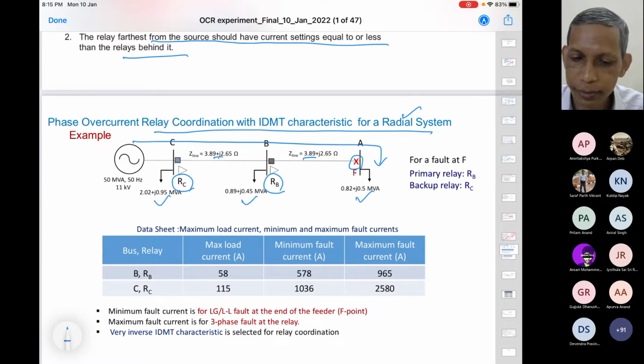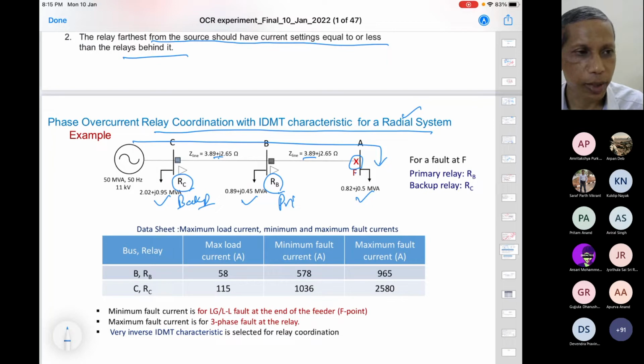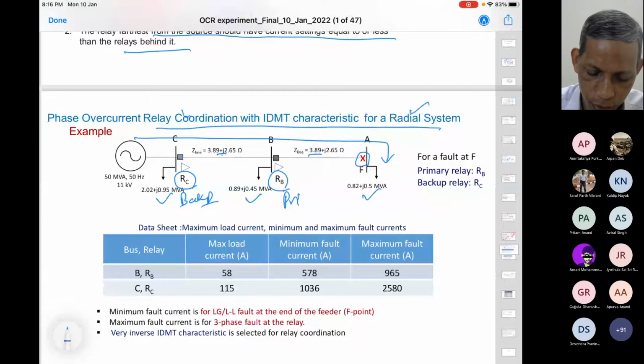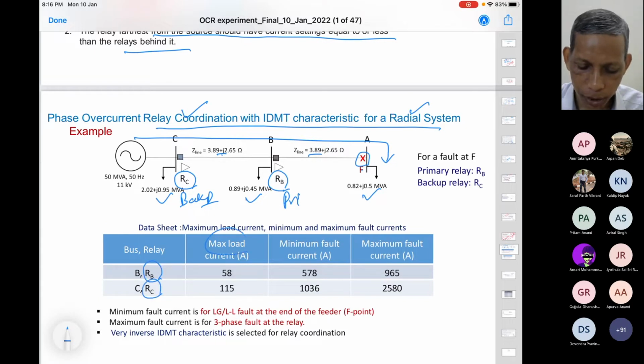For a fault at F, RB is the primary and RC is the backup. RB is the primary and RC is the backup. Agree? So that we have to see from that perspective. Okay. So if you see this, the data required for this coordination task is the set of data for RB and RC. Maximum load current.